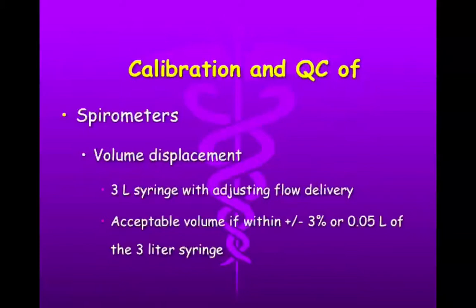So typically, if you're using a 3-liter syringe, it's acceptable if the volume is within 3% or 0.05 liters of the 3-liter syringe. So if they're not, you have to go back through and try to recalibrate and figure out what's going on. Maybe you have a leak in the system, something like that. Fortunately, today's machines are pretty good about guiding you and telling you what might be the problem, so that's kind of nice. You don't have to do quite as much research or digging like you used to.